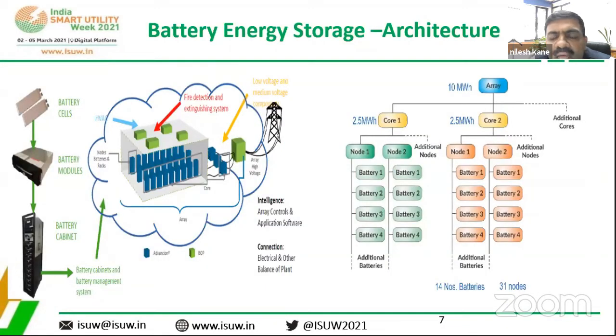So this is a simple architecture. It is a 10 megawatt hour system, and there are 4 cores of 2.5 megawatt hours each, because we have a typical topology of 66 by 11 kV grid on which we have 25 MVA transformers. Both the transformers are supported, with 2 11 kV feeders interconnected with the 2.5 megawatt hour cores. In every core there are 2 nodes, and in every node there are 14 batteries, each of capacity 6.5 kilowatt hours. It is integrated with the smart inverters, and integrated appropriately through isolation transformers. Next slide.